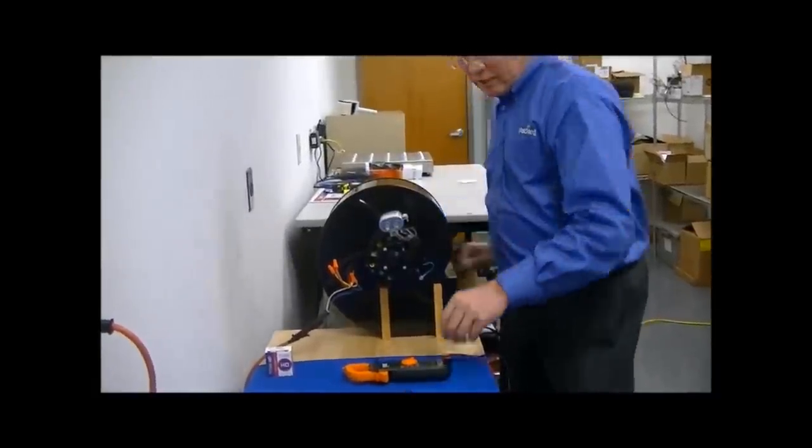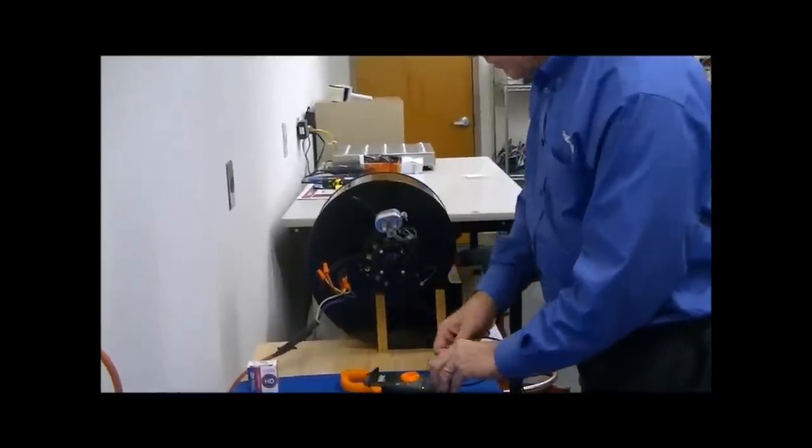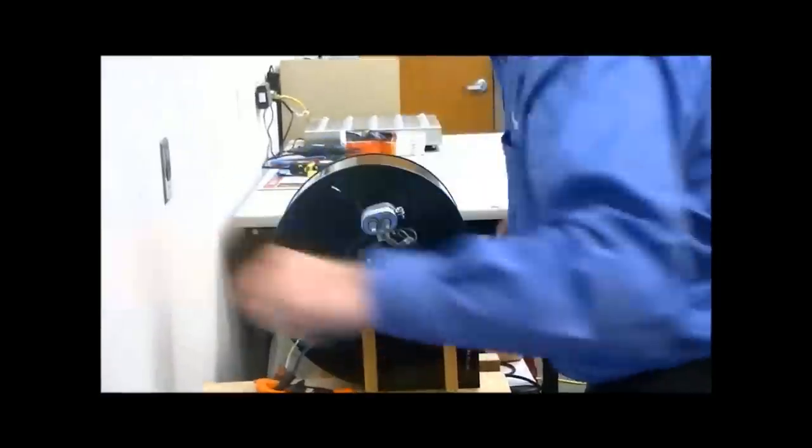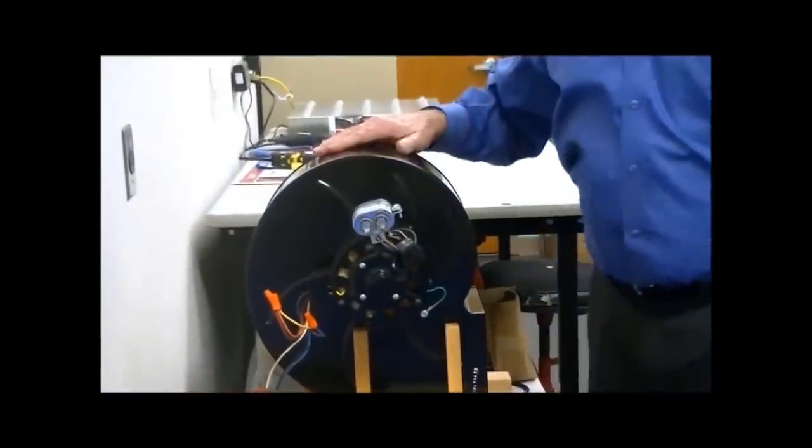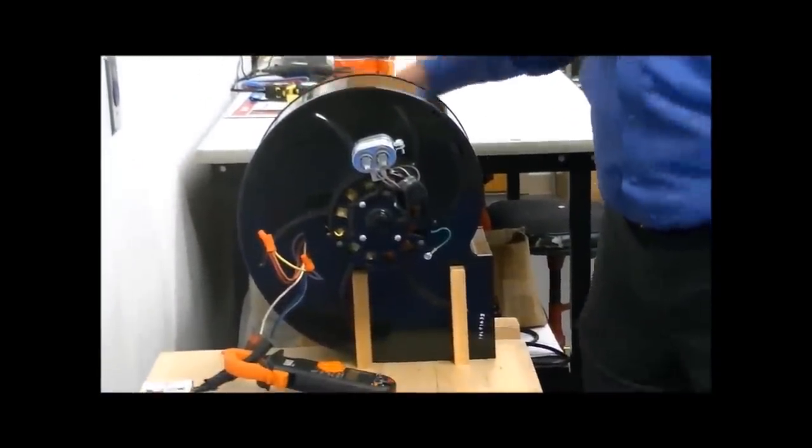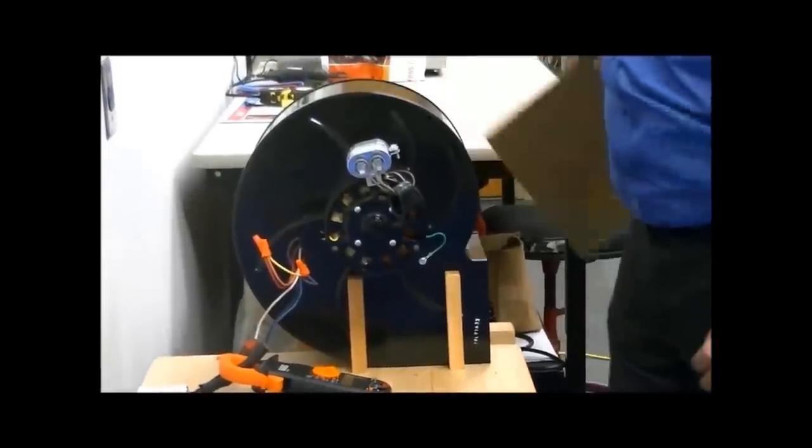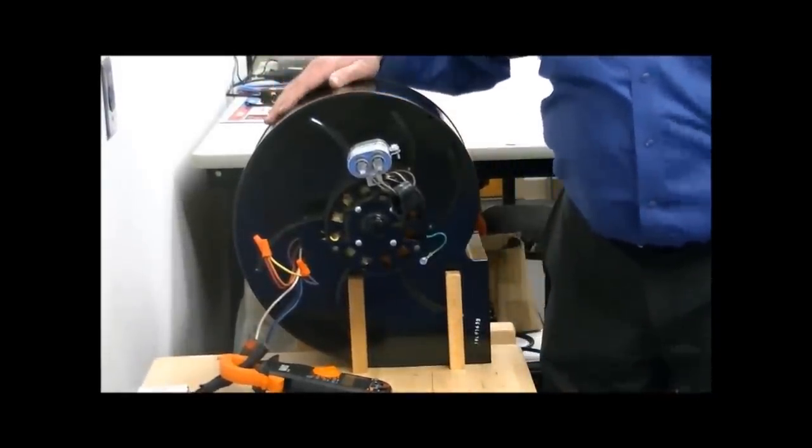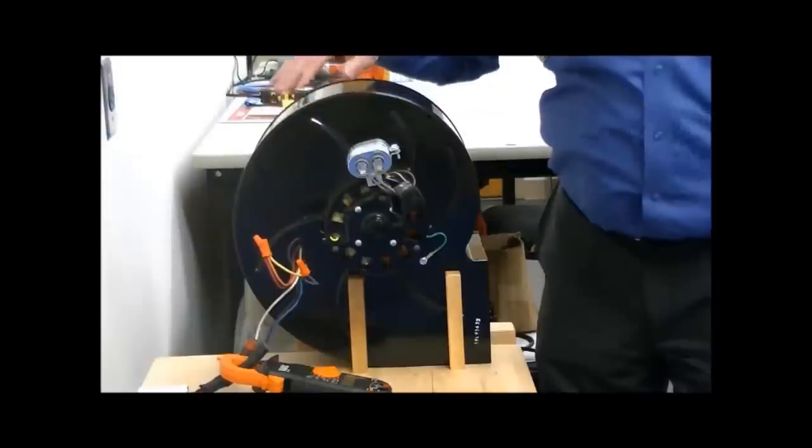As we restrict the air, we can determine the performance of the motor strictly by measuring the amps. In free air, this motor is operating at 3.2 amps.